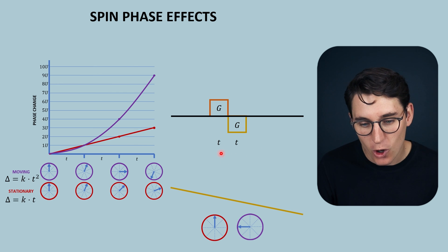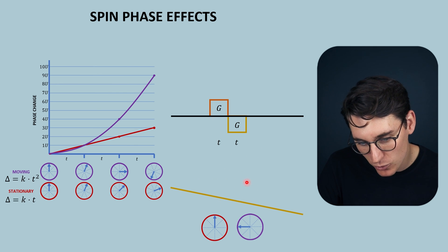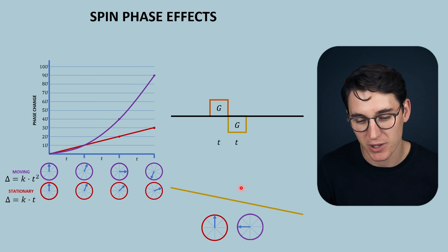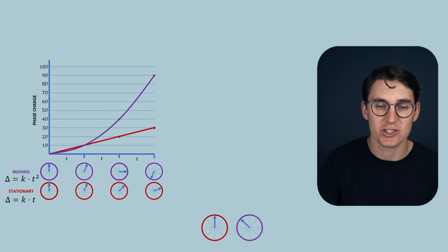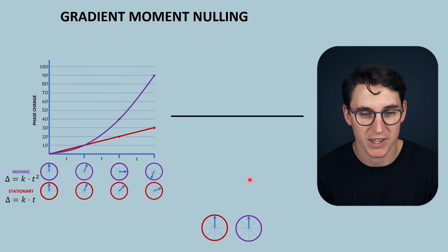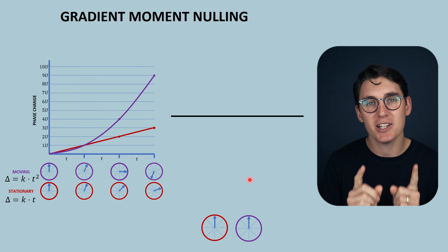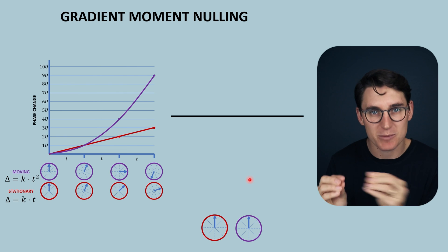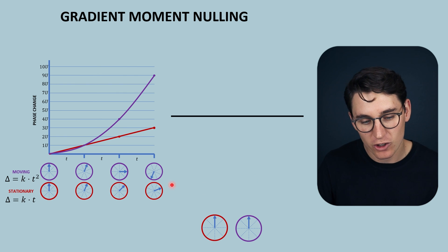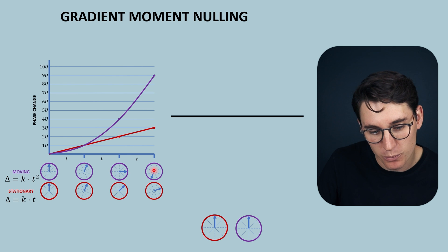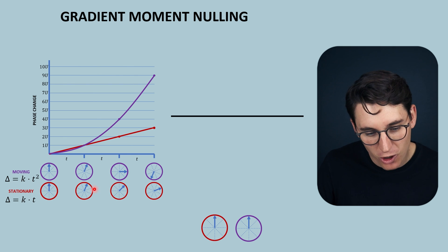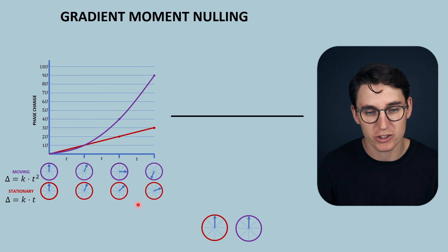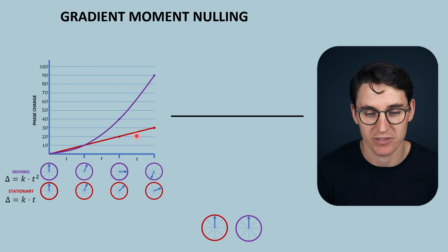It turns out we can compensate for the movement of moving spins through a slice whilst a gradient is being applied using something known as gradient moment nulling. Gradient moment nulling compensates for this phase loss as spins move through a slice, and it also still compensates for phase loss in stationary spins.